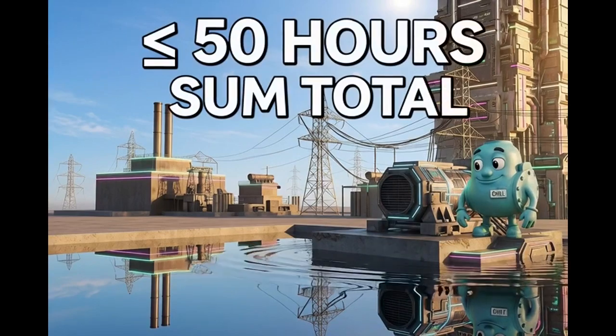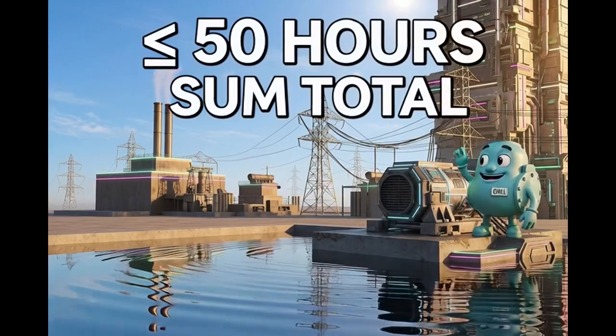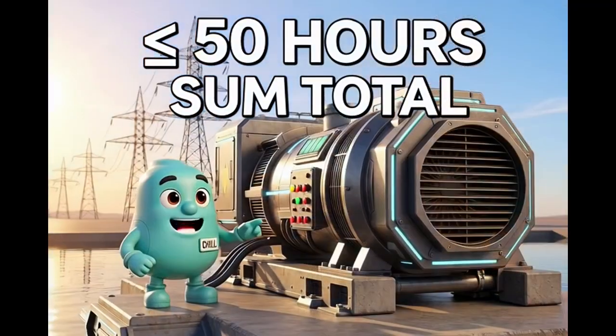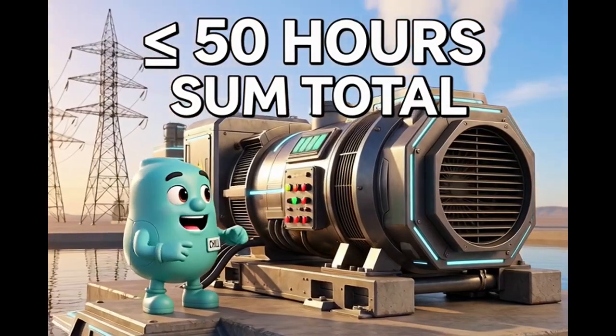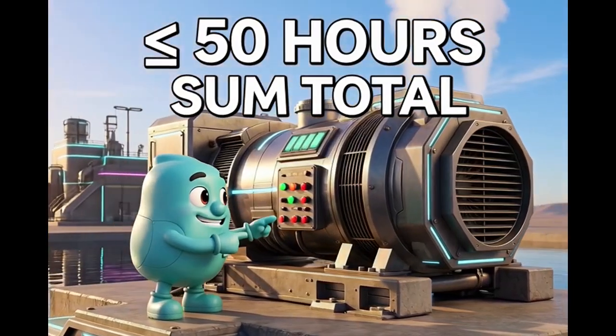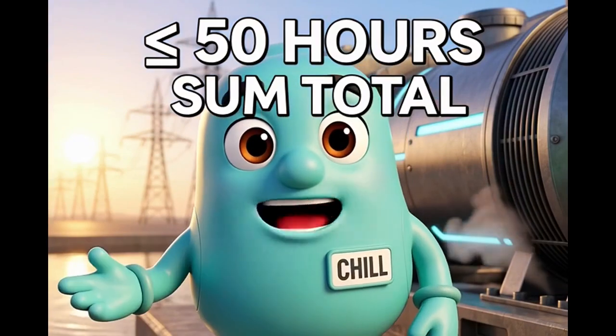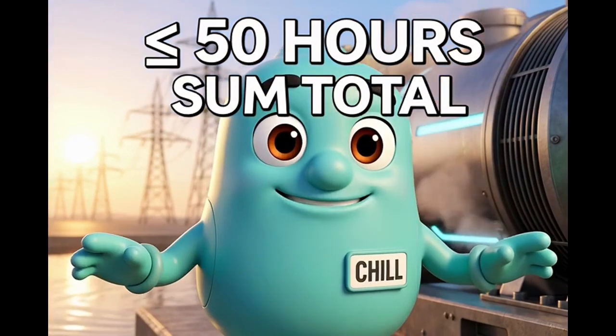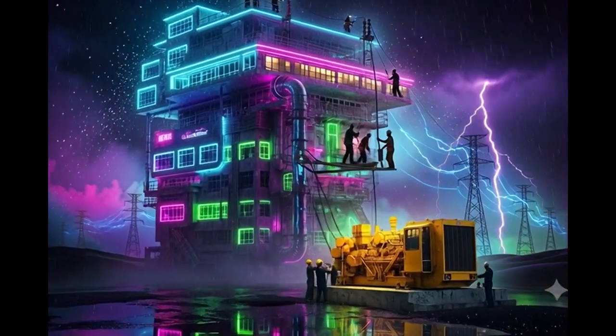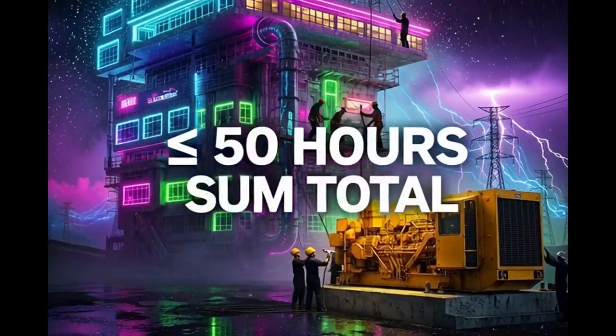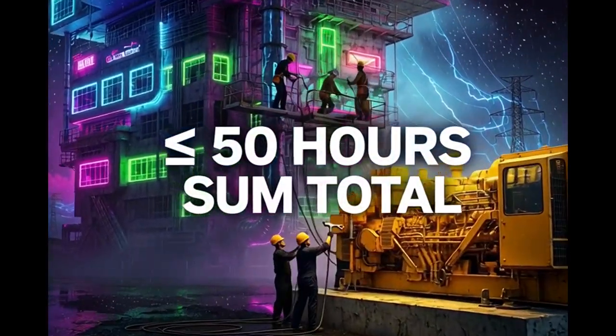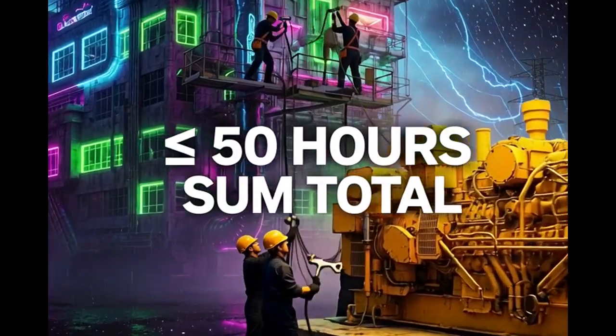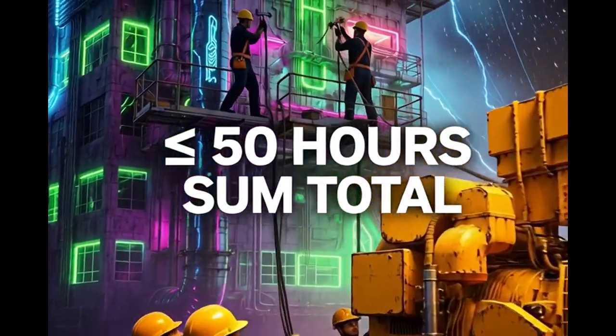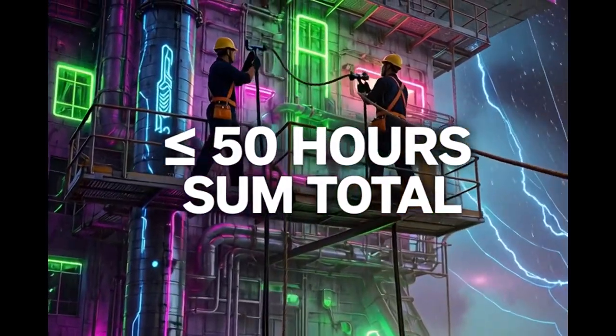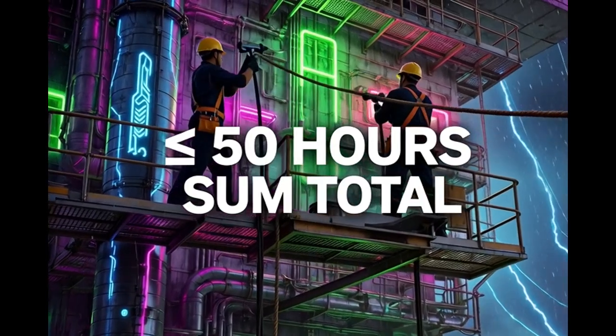Track every single one. Planned utility infrastructure maintenance is a non-emergency use. All these hours go into your 50-hour combined annual total for the 5 allowed non-emergency activities. Keep the running total under 50 hours per engine and log everything. Planned repairs to building utility connections count toward the 50-hour non-emergency total. Everything across all 5 allowed non-emergency uses has to stay under 50 hours combined per year per engine. Log the purpose and hours every time.